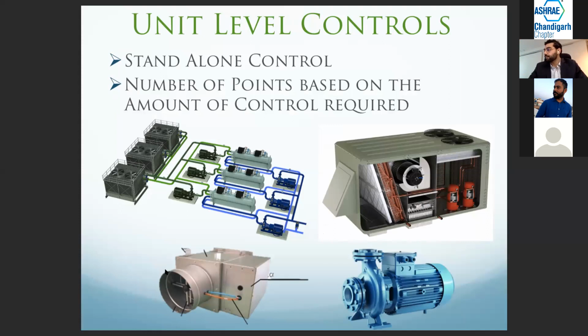I know this shows a system, but it's still unit level controls we're talking about. The cooling towers and the pumps may have a controller. The fan VAV box will have a controller. The pump will have a controller. All these are unit level controls. These controls are programmed in a way that the controller is able to make the equipment work regardless of any input from the system controller as well. We'll go into that again. I don't want to get ahead of myself.